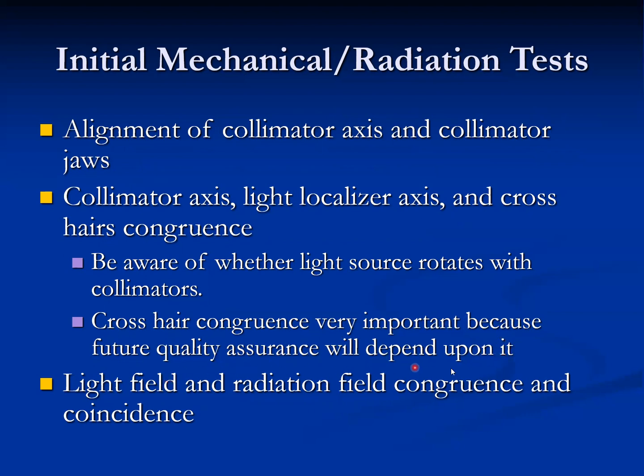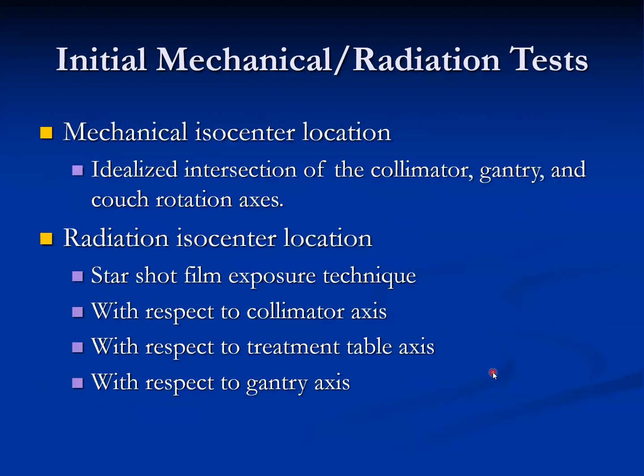Light field and radiation field congruence, and mechanical isocenter location — the idealized intersection of collimator, gantry, and couch rotation axes — should be verified. Radiation isocenter location is verified using the star shot film exposure technique with respect to the collimator axis, treatment table axis, and gantry axis.